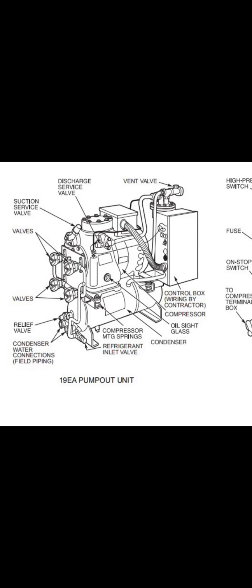So we have to do pump down. What we do is keep open the liquid line valve from condenser to cooler, and the upper valve. The discharge valve, which is an isolation valve, we have to close. Sometimes in the plant room they already have piping for pump down.